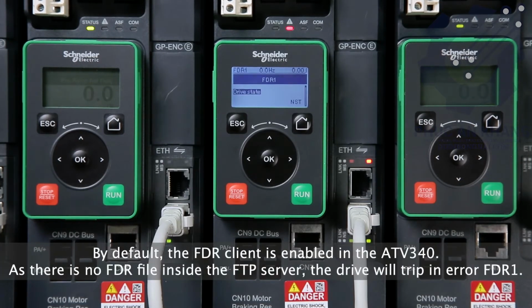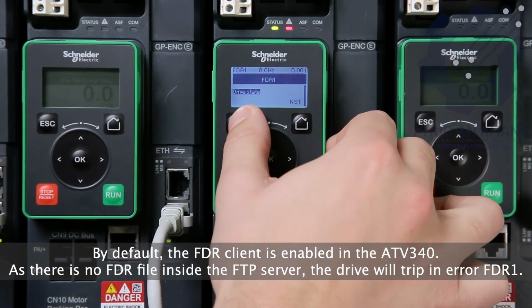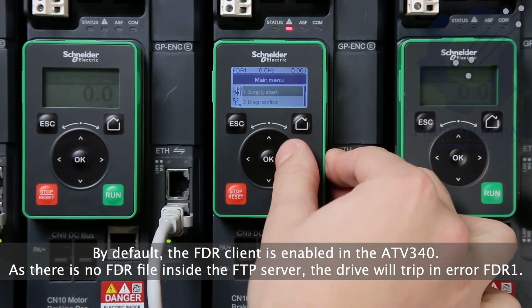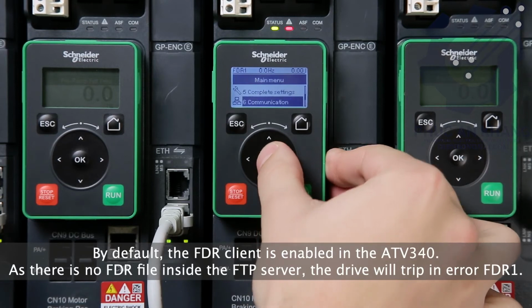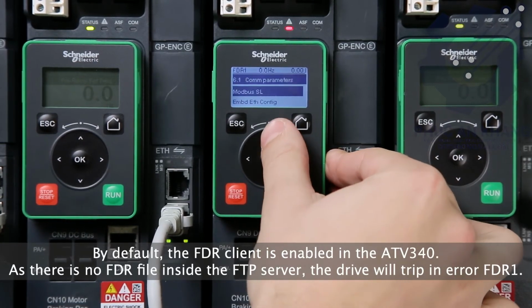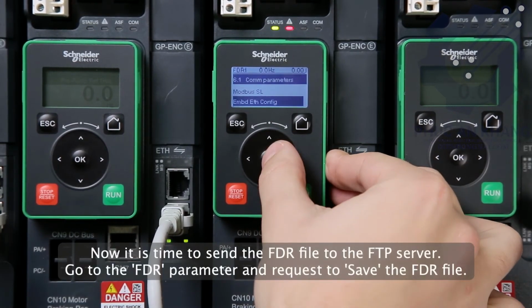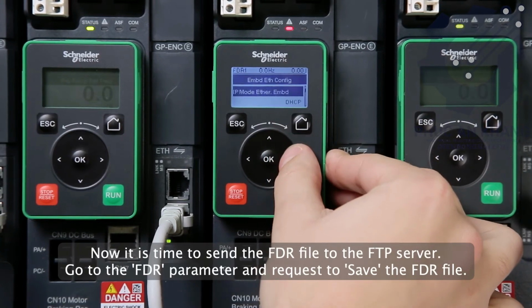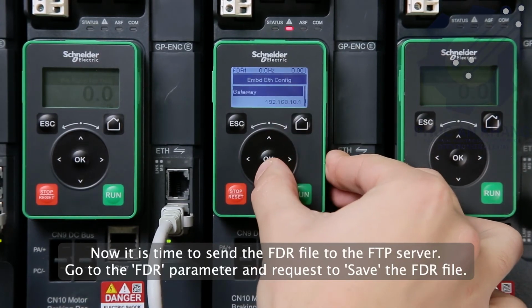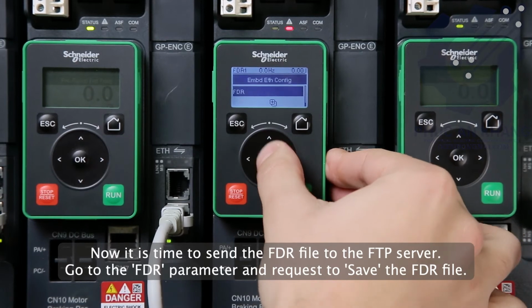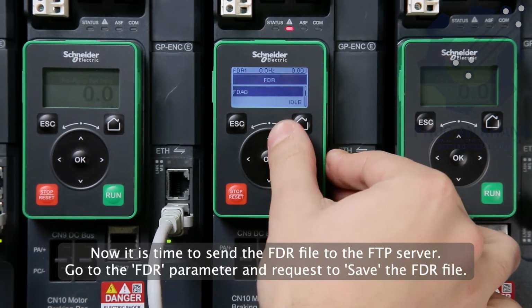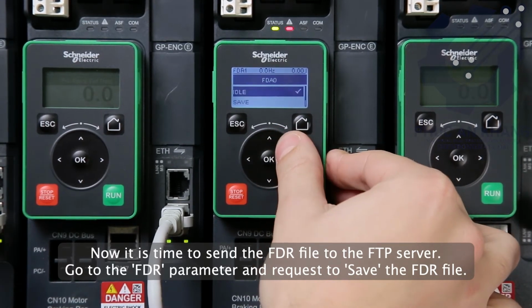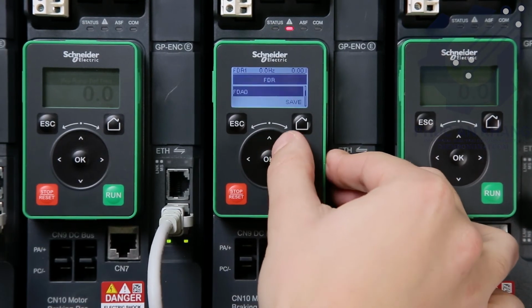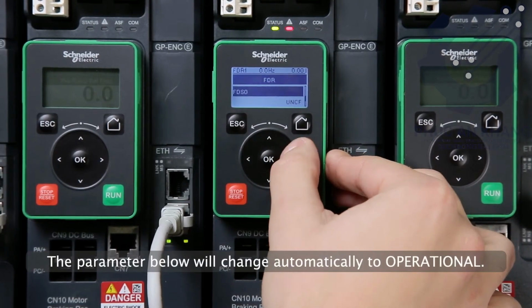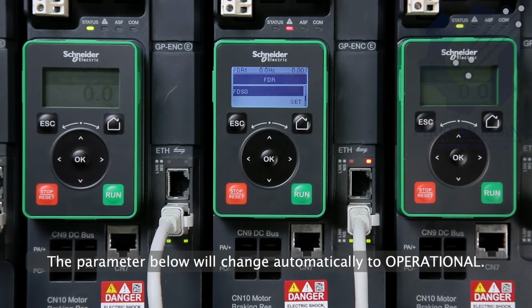By default, the FDR client is enabled in the ATV340. As there is no FDR file inside the FTP server, the drive will trip in error FDR1. Now it is time to send the FDR file to the FTP server. Go to the FDR parameter and request to save the FDR file. The parameter below will change automatically to operational.